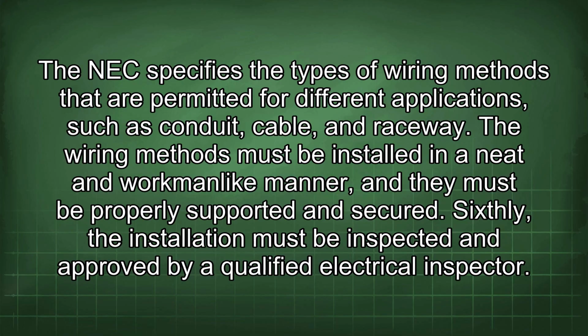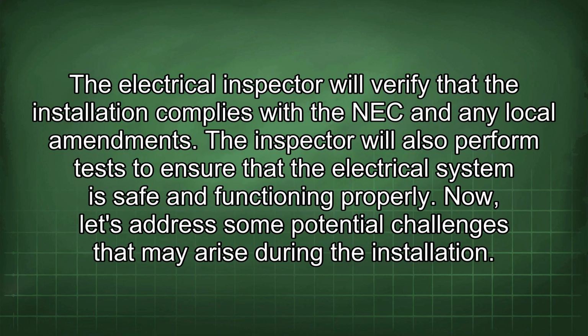Sixthly, the installation must be inspected and approved by a qualified electrical inspector. The electrical inspector will verify that the installation complies with the NEC and any local amendments. The inspector will also perform tests to ensure that the electrical system is safe and functioning properly. Now let's address some potential challenges that may arise during the installation.